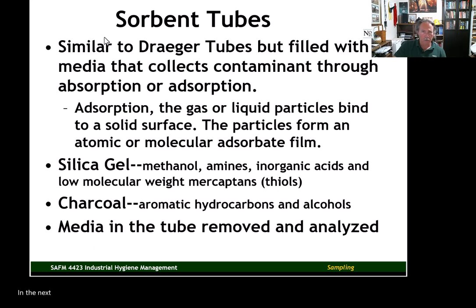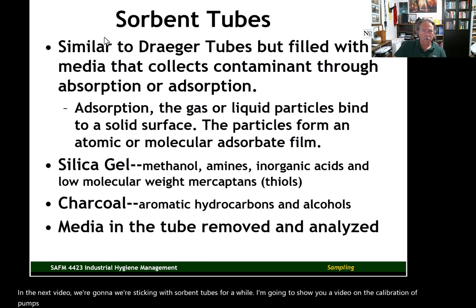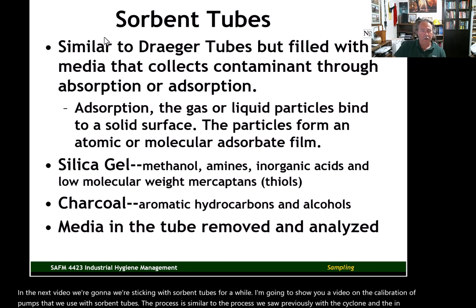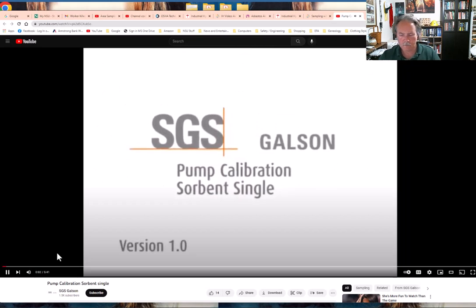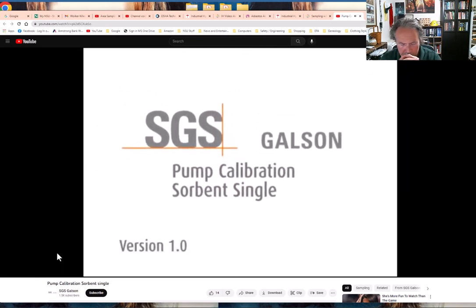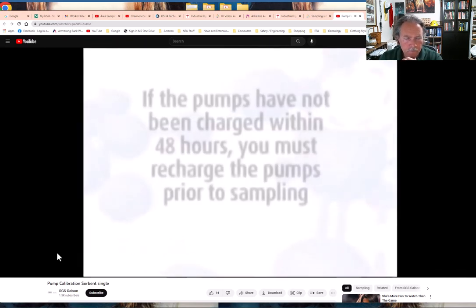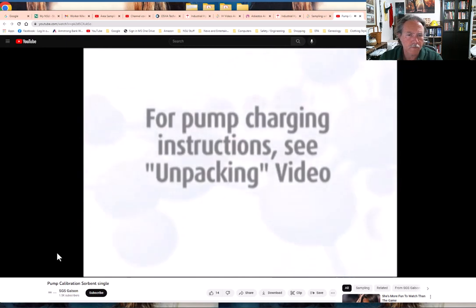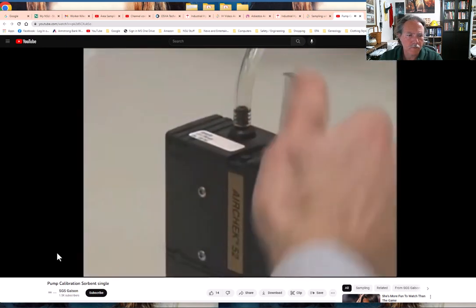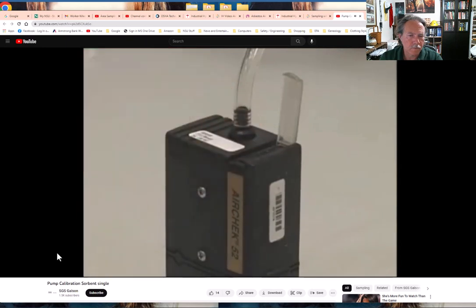In the next video, we're sticking with sorbent tubes. I want to show you a video on the calibration of pumps used with sorbent tubes. The process is similar to what we saw previously with the cyclone and particle impactor, but there are some differences. To calibrate the pumps, they must be charged. If the pumps have not been charged within the past 48 hours, you must recharge prior to sampling. Start the pumps so they can warm up — they need to run at least 3 minutes before you begin calibration.